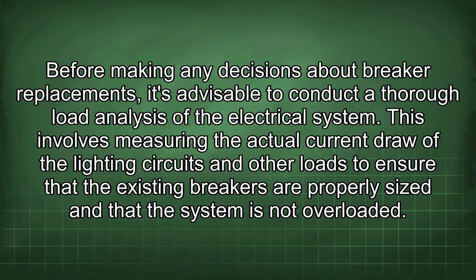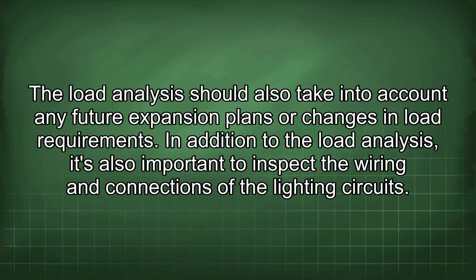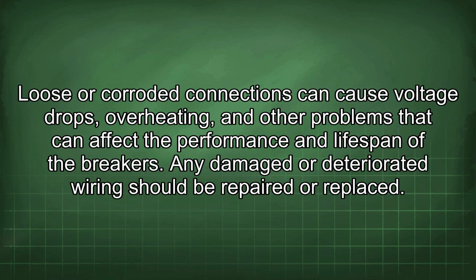Before making any decisions about breaker replacements, it's advisable to conduct a thorough load analysis of the electrical system. This involves measuring the actual current draw of the lighting circuits and other loads to ensure that the existing breakers are properly sized and that the system is not overloaded. The load analysis should also take into account any future expansion plans or changes in load requirements. In addition to the load analysis, it's also important to inspect the wiring and connections of the lighting circuits. Loose or corroded connections can cause voltage drops, overheating, and other problems that can affect the performance and lifespan of the breakers.